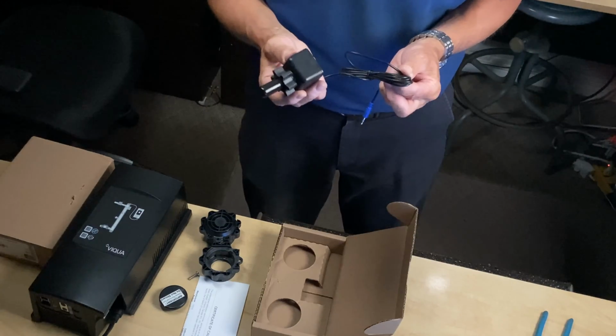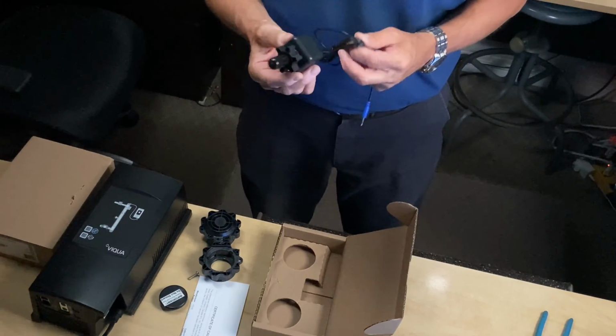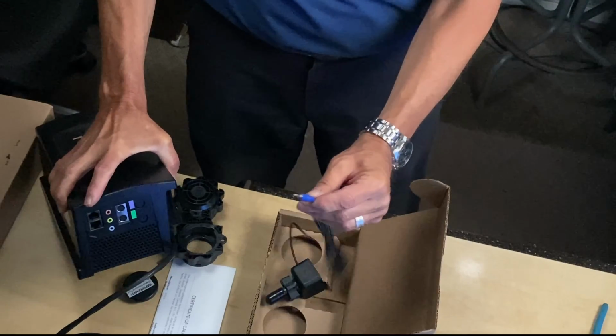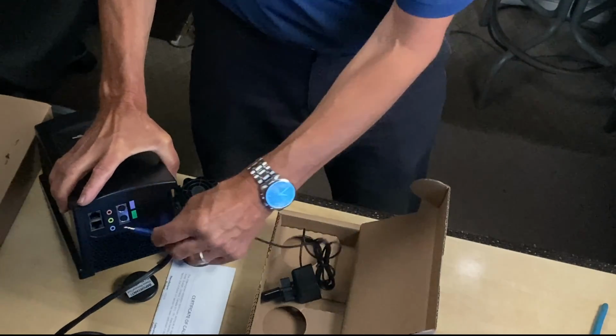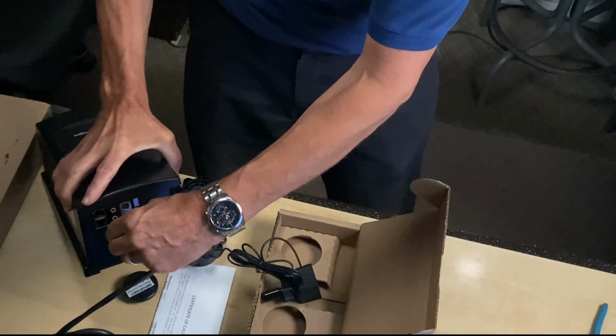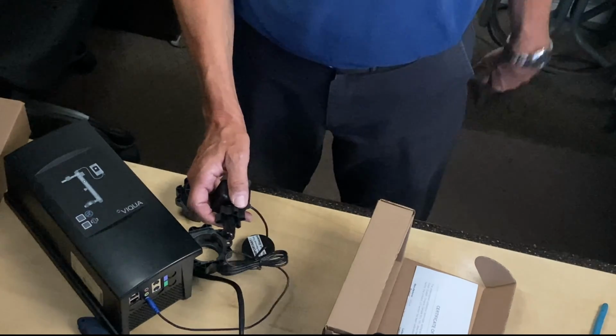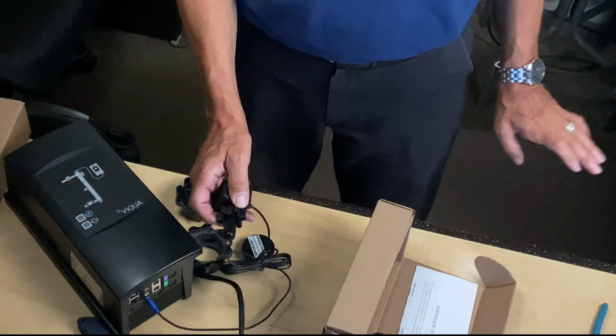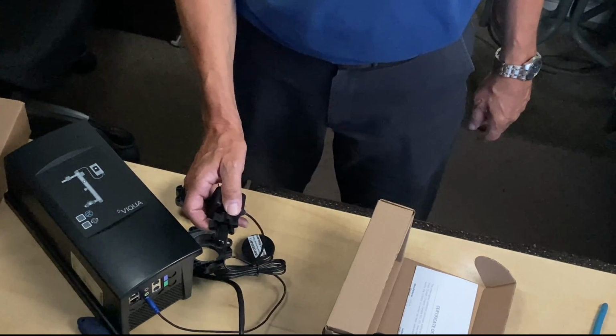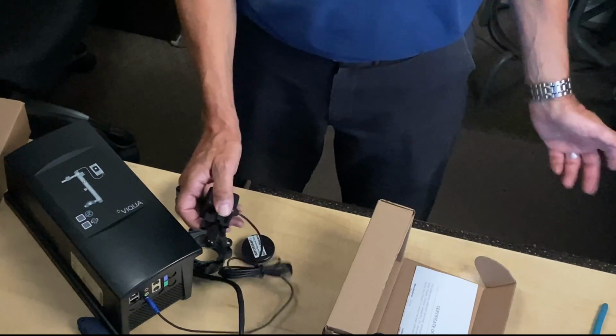And this is the UV intensity sensor, which needs to be cleaned periodically, once a year, or if you notice that the UVT, the reading on the controller, shows that it's dropping, that tells you it's also time to clean the sensor. And as you can see, the connector is blue, so it's color-coded, so you can just plug it right in. So together with the sensor, the controller gives readout and alarms when the sensor is reading minimum UV dosage, or it's unplugged, or it just needs service.